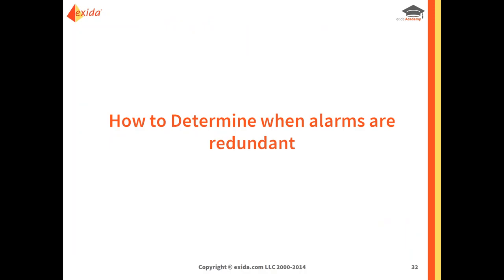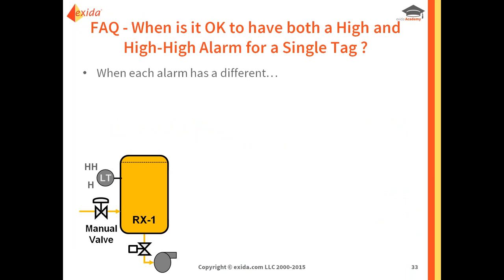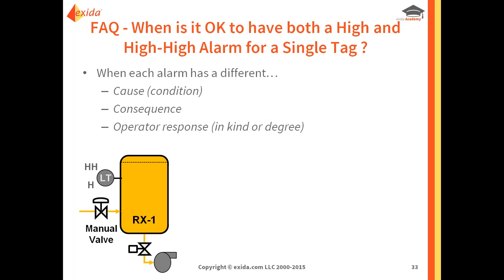How do we determine when alarms are redundant — for example, when is it okay to have both a high and a high-high alarm? In the past, a high-high might have been configured as a backup in case the operator missed the high alarm. That's not a productive approach. Instead, for each potential alarm, analyze the cause, consequence, and corrective action. Something must be different between the two alarms for those three criteria. If nothing is different between the high and high-high, you have duplicate alarms and don't need both.